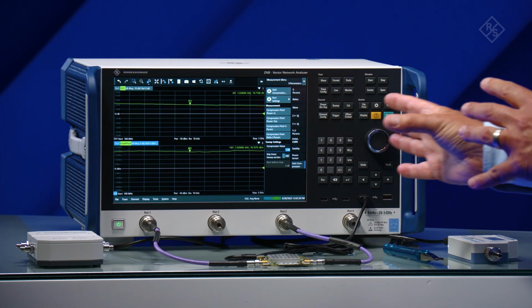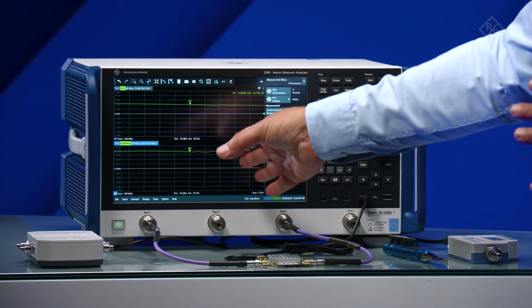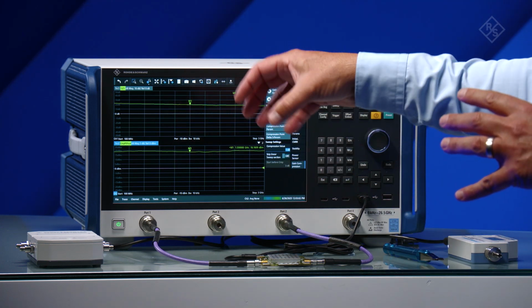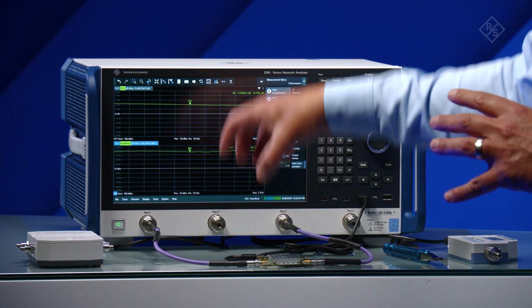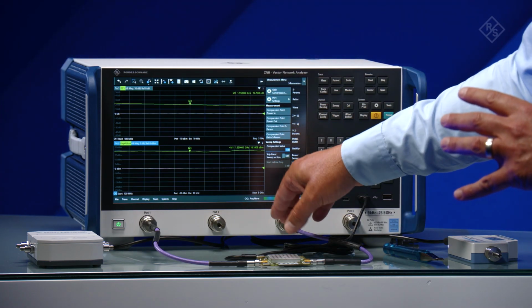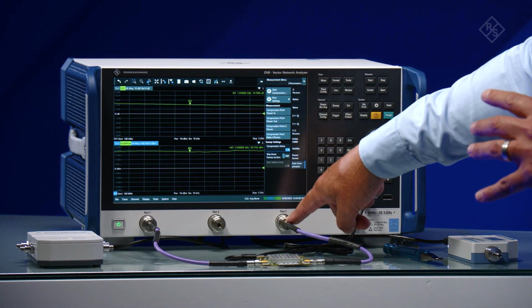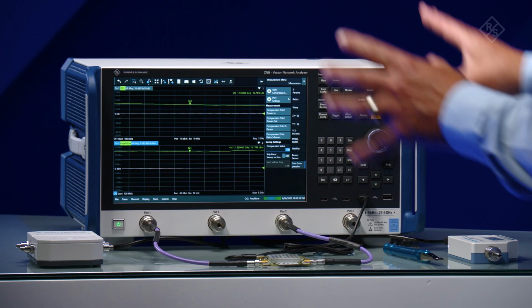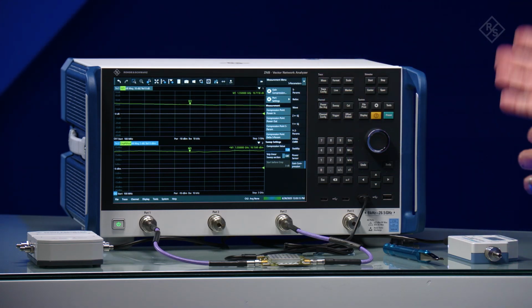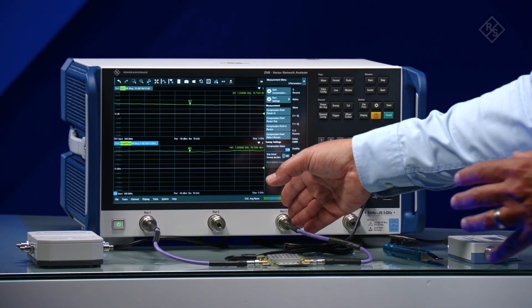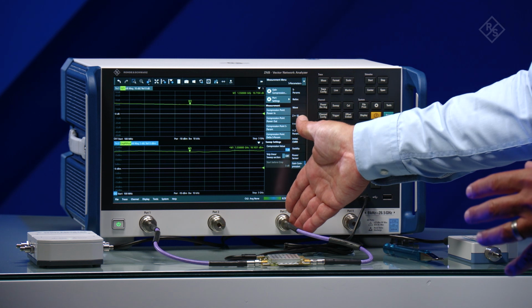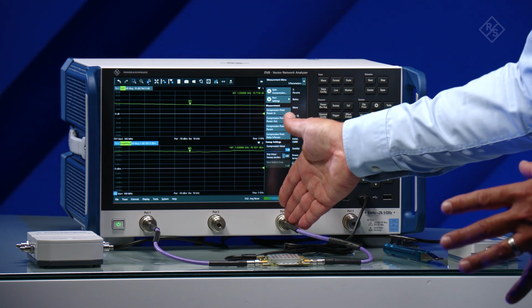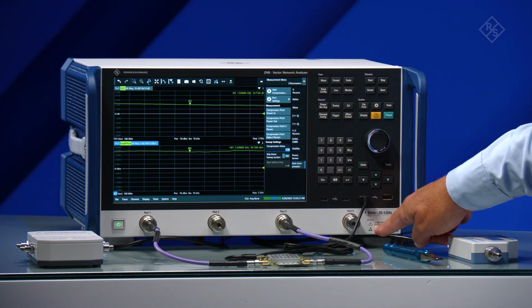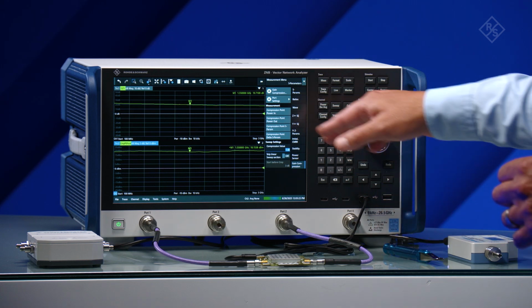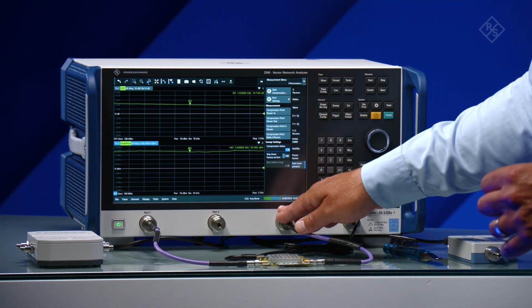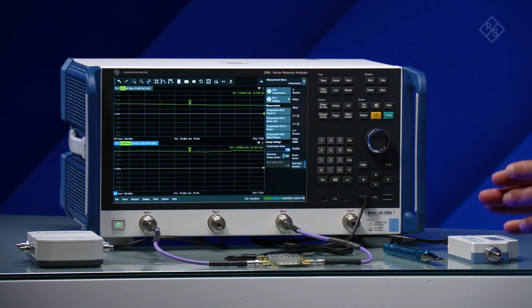Before we do, we want to be absolutely sure that this compression value that we're measuring is coming from the device under test and not down to our receiver, because we're putting too much power from the DUT into our receiver. On the ZNB3000, we recommend a maximum operational power of around plus 13 dBm. That's not the maximum power shown on the front panel, which is the damage level. That's the maximum power we can put in here before any effects of nonlinearity might be observed.